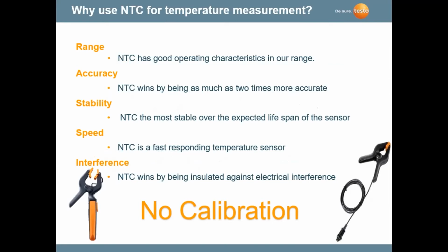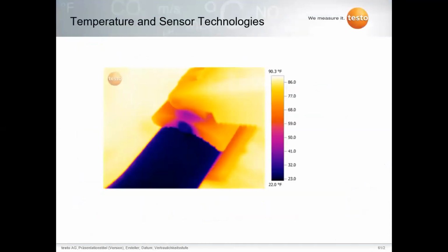But with NTC, just keep in mind that NTC has a very good operating range for temperature measurement in refrigeration systems. Its accuracy is much better than the thermocouples. And the big thing really is that there's no calibration. And most of you that are using a Testo, whether it's a plug-in probe or a wireless probe, you know that when you turn those two probes on in ambient temperature, you're going to get roughly the same reading. What I mean by roughly the same reading, it's going to be plus or minus 1 degree difference, and even less than that. It's remarkable how stable these NTC probes are.